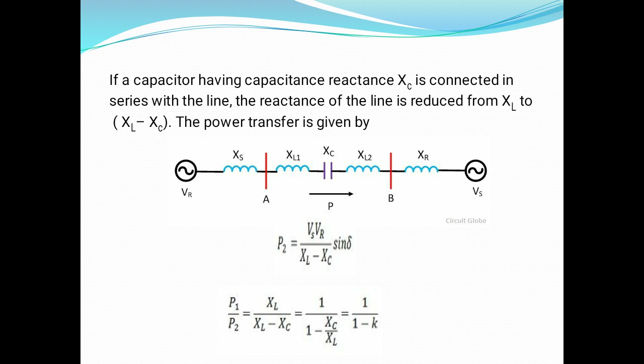For example, if K is equal to 0.5, then P2 / P1 is equal to 1 / (1 − K), or 1 / (1 − 0.5). So its value is 2 times. It means if the compensation factor is 0.5, then power transferred by the transmission line becomes double. It means a transmission line can transfer double power, 2 times.